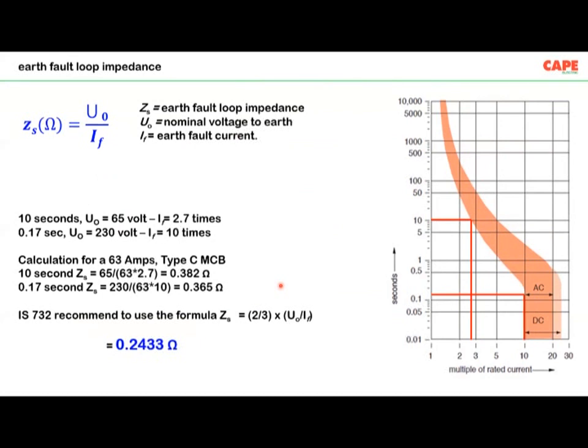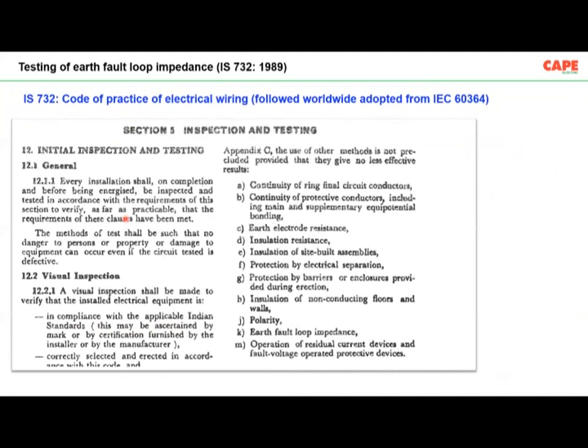earthed system, as I said, earthed and unearthed system. In an earthed system, safety is achieved by protective equipotential bonding and automatic disconnection of the supply. For disconnection, there is a maximum time. So within a certain time, you are supposed to disconnect. Otherwise, the fault will create fire or electrocution. Now, for disconnecting your MCB within this time, the fault loop impedance is very important, which is recorded in several standards. What I am showing is IS 732-1989, a very old standard, 32 years old.